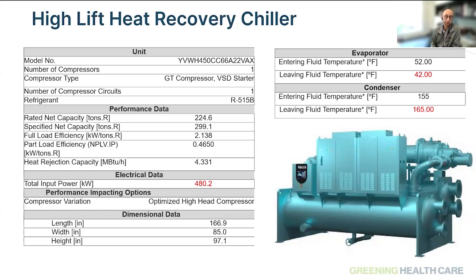Yeah, you bet, and thanks for having me. We were approached by Ecosystem saying that they are working on this design for the Lakeview project, where they have an existing facility and they don't want to downgrade the entire hydronic heating system. Fortunately, we had the technology and the R&D in place where we right-sized our heat recovery heat pump chillers to serve that high temperature market. So you don't necessarily need to replace your heating coils, your piping, your pumps and everything. There is technology out there, and it's not just from us, that can provide high temperature heating up to 180 degrees Fahrenheit for those existing facilities.